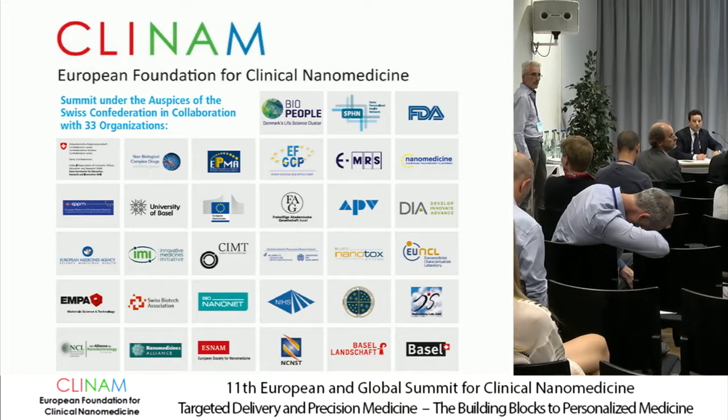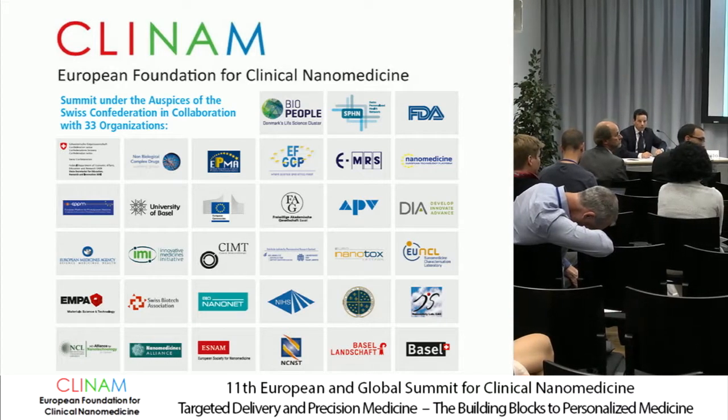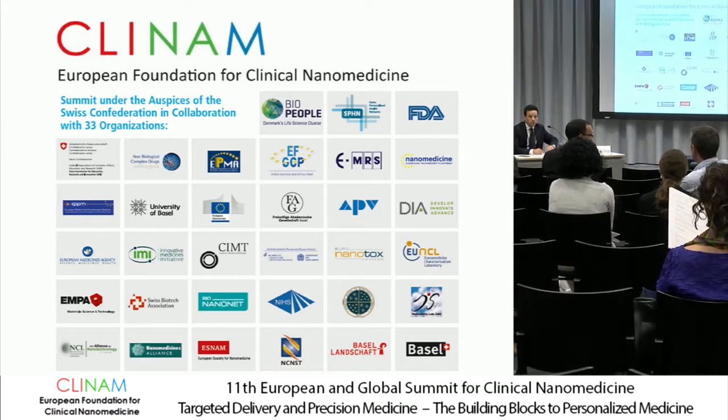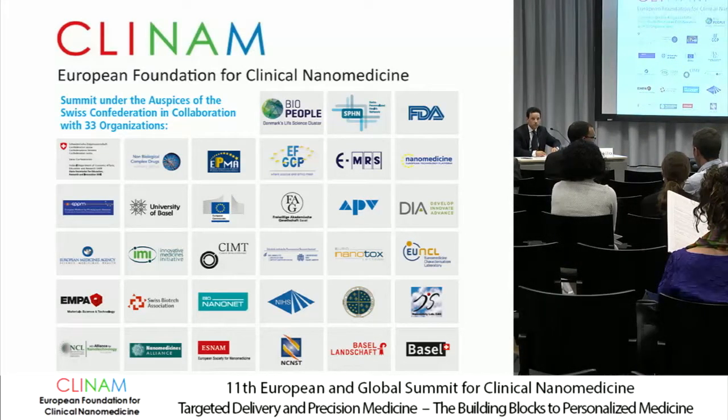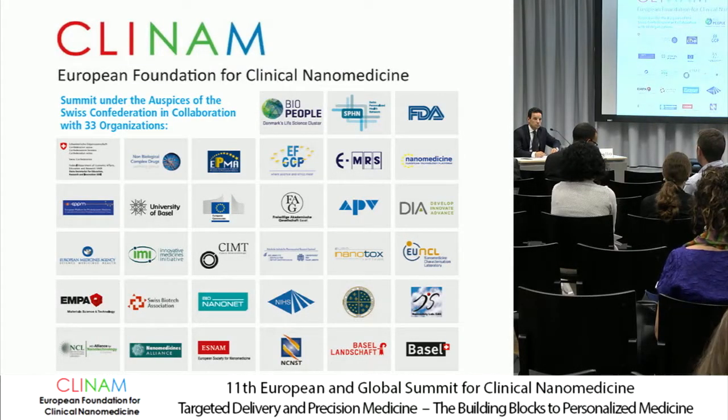In fact, I wanted to say that here we can use as reference, I don't know if you agree, the pharmacopoeias dealing with laser diffraction, which is a technique covering a wider range. All these pharmacopoeias provide procedures to evaluate the repeatability and the intermediate precision, and they can be implemented in DLS as well. The issue is the acceptance criteria: you need to take into account the kind of material that you are analyzing, and perhaps the acceptance criteria proposed in those pharmacopoeias can work or cannot work. But at least it can be a good reference, and in some cases we are using them as reference.